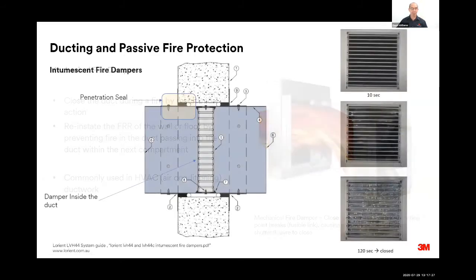Now, another method of fire damper is an intumescent damper, where there are materials inside the damper that, when exposed to heat, expand. They can expand 10 times or more, and they activate really quickly, and they will close the duct off by that method. And one of the advantages of that is that there's no real moving parts. So that's the two methods of fire protecting ductwork through fire dampers.